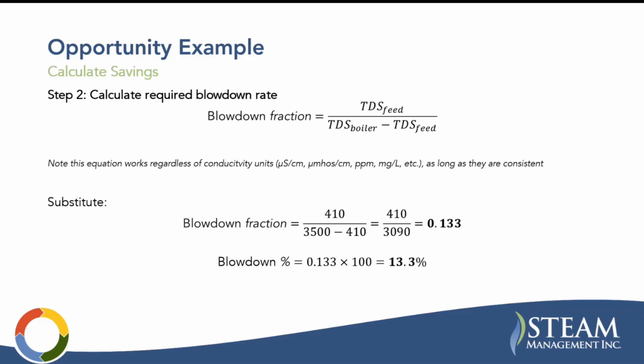Then from there, we're going to calculate the blowdown rate. So we have the TDS of our feed water. We have a conservative boiler TDS level of 3,500 micromhos. That's kind of typical for a fire tube boiler. Note that this top equation, like I mentioned, works with all different units of conductivity because the units cancel out. So it's a ratio, right? If you have everything in microsiemens or parts per million, whatever, that equation still works. But in the end, we come up with a blowdown percentage of 13.3%.